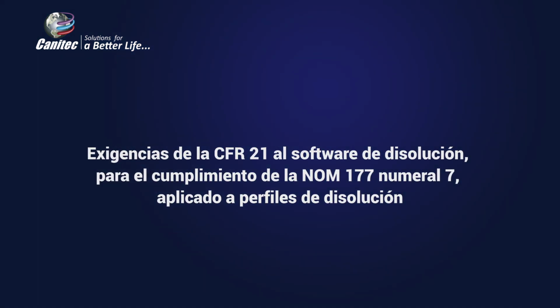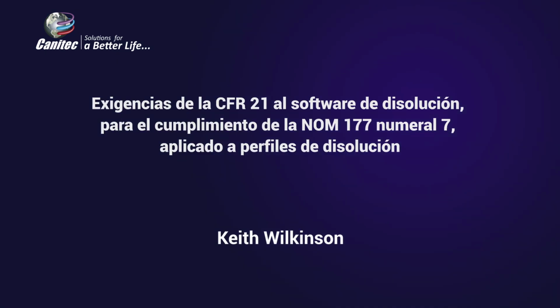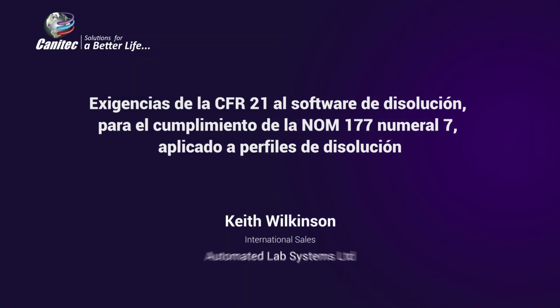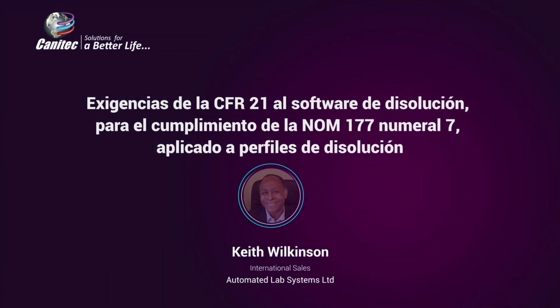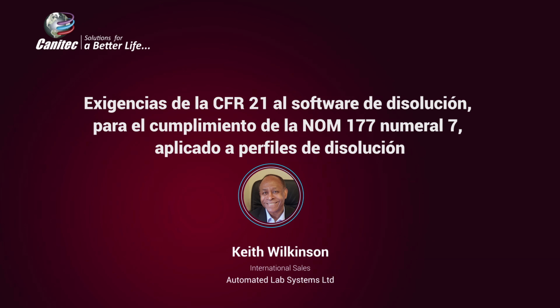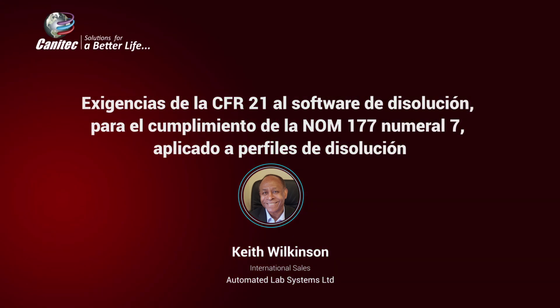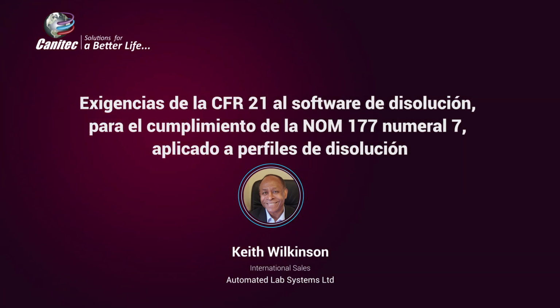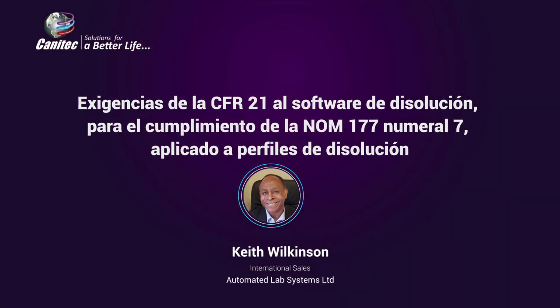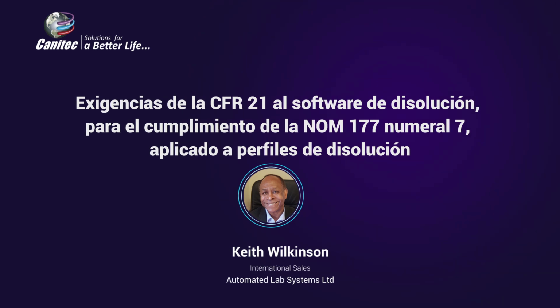So the software is asking me to remove the tubing from my blank and insert it into my standard. It's now pumping my standard and it acquires a reading for my standard. And I would do the same for my second standard. If the test passes, we can define the criteria under which the test should pass. I'd enter the criteria of 2%, it told me it passed, and I can continue. You can configure that if the test does not pass, the user cannot continue, they can only retry.